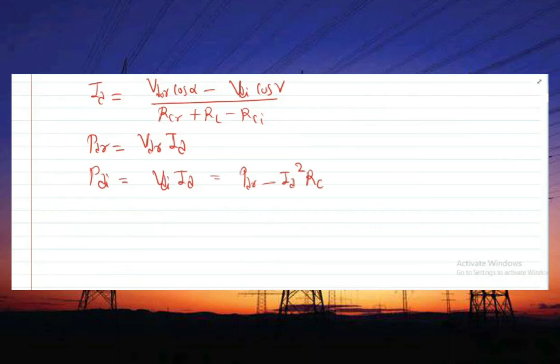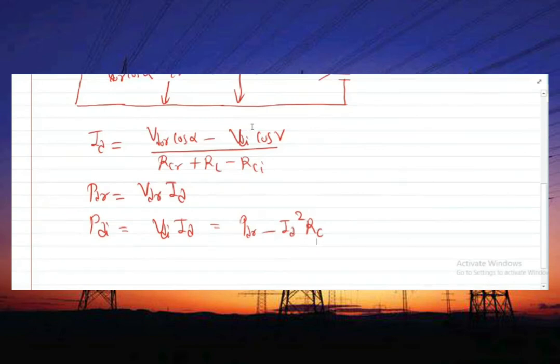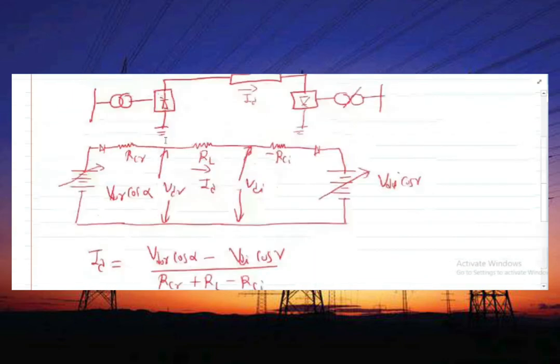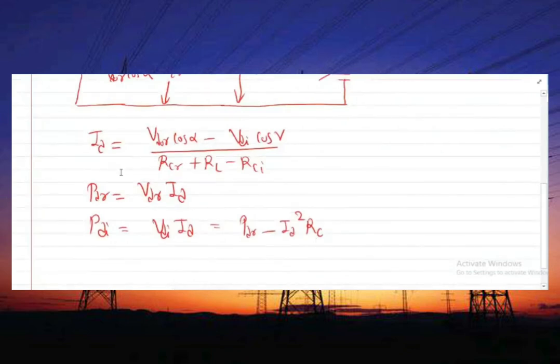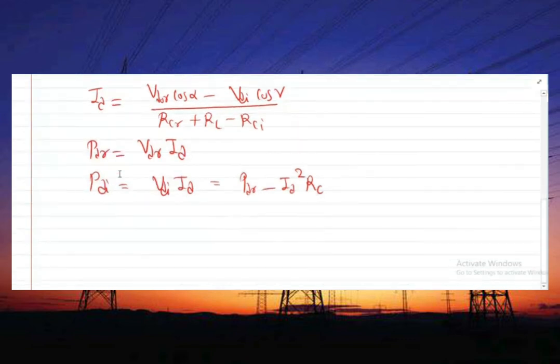The direct voltage at any point of the line and the current can be controlled by controlling the terminal voltage at the rectifier terminal and the inverter terminal. This is comprised by the control in the gate control or the valve ignition control and control of the AC side by tap changing control.